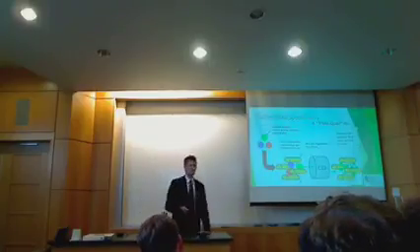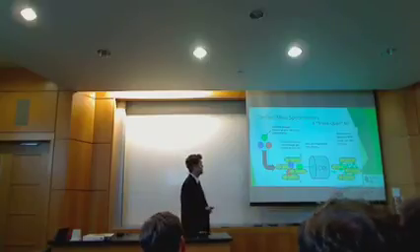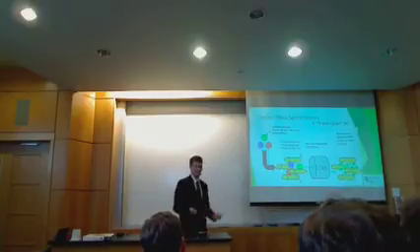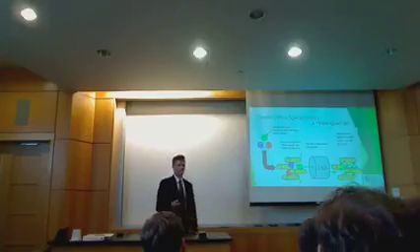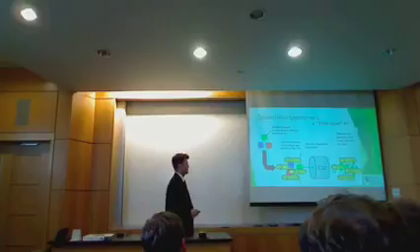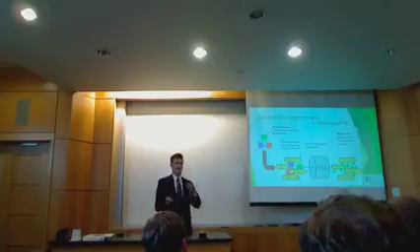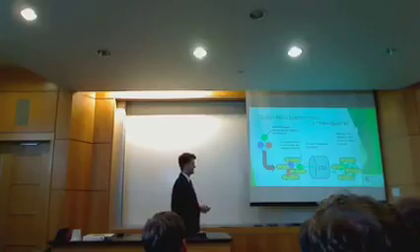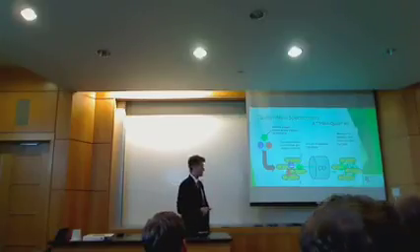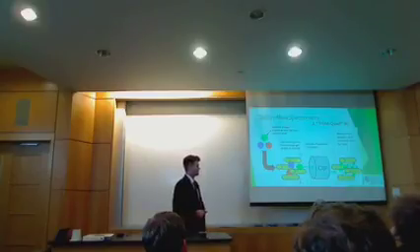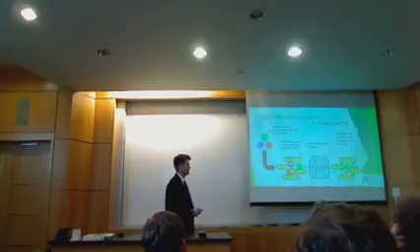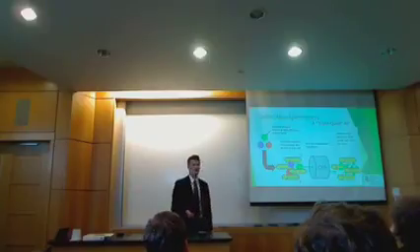How do we actually measure things in a mass spectrometer? Well, in the case of the lab I was working in, we use what's called a triple quad mass spec, which means it has three quadrupoles. Very nice name. What we do is we begin with a lot of different analytes, so we don't have to do any filtration. The first quadrupole is an electric field that we can oscillate back and forth. Based on the frequency of the oscillation, a certain mass to charge ratio will pass through, but other size particles or other charged particles will fall out of that path and not make it through in a straight line.